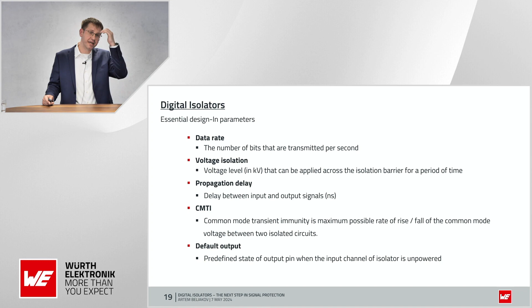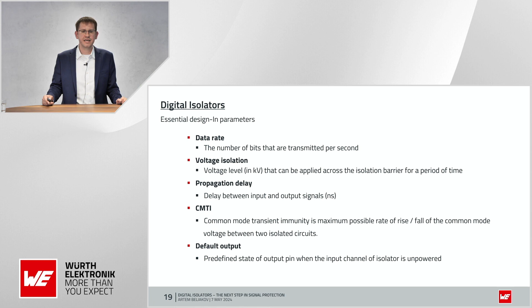Next, CMTI, or common mode transient immunity, is the maximum possible rate of rise or fall of the common mode voltage between 2 isolated circuits. And last, default output: the predefined state of the output when the input channel of the isolator is unpowered.